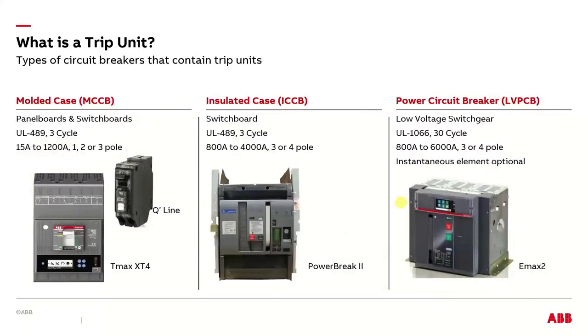I'm breaking this down into what kinds of breakers the trip unit goes into, and generally there are three classes. There's your molded case circuit breaker, abbreviated MCCB, and that's what you'd see in panel boards and switchboards. It's UL489, the UL standard for essentially panel breakers and switchboard breakers. Typically 15 to 1200 amp, 1 to 3 pole, and it's the most common. 99% of the breakers that you'll see are going to fall into that range.